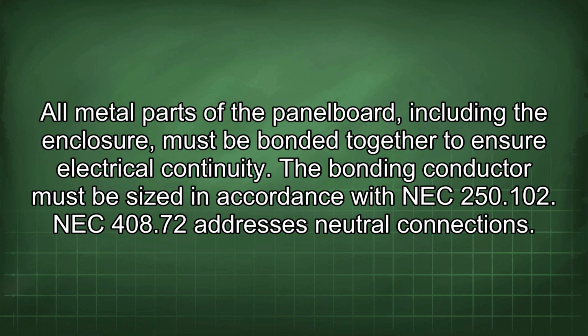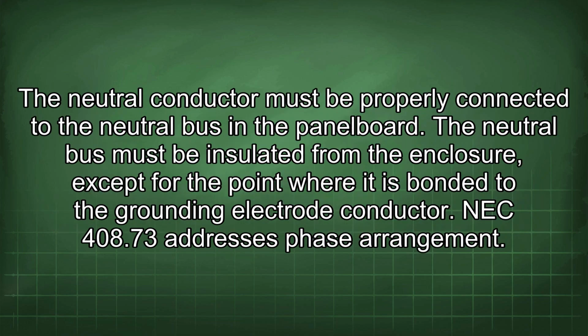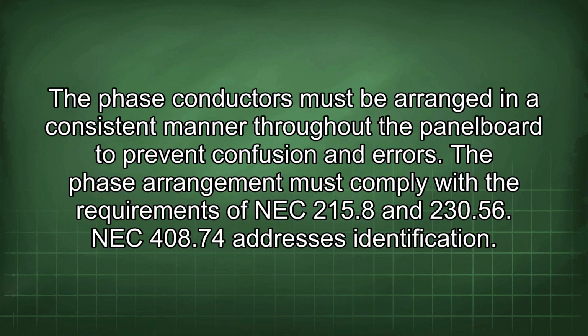250.102. NEC 408.72 addresses neutral connections. The neutral conductor must be properly connected to the neutral bus in the panel board. The neutral bus must be insulated from the enclosure except for the point where it is bonded to the grounding electrode conductor. NEC 408.73 addresses phase arrangement. The phase conductors must be arranged in a consistent manner throughout the panel board to prevent confusion and errors. The phase arrangement must comply with the requirements of NEC 215.8 and 230.56. NEC 408.74 addresses identification.